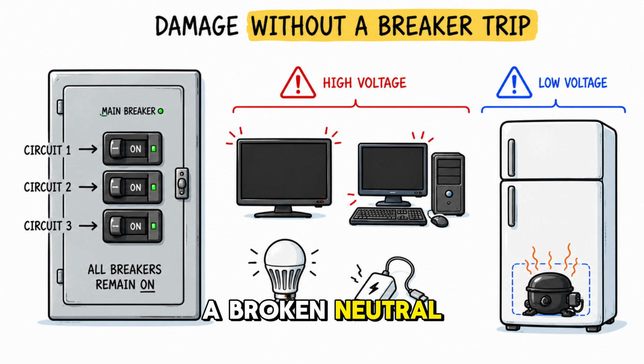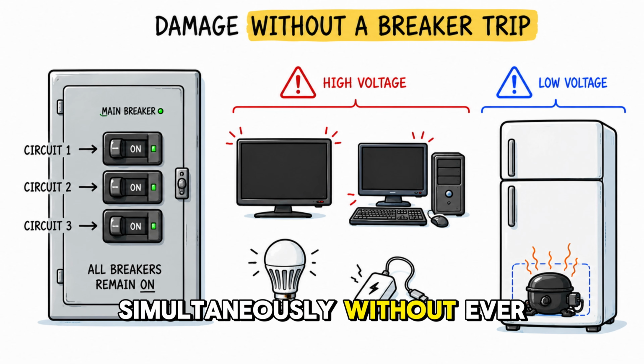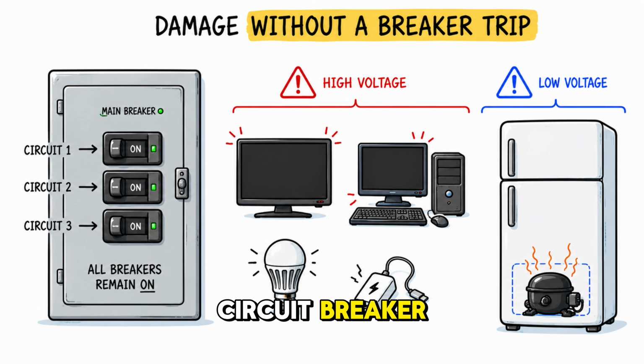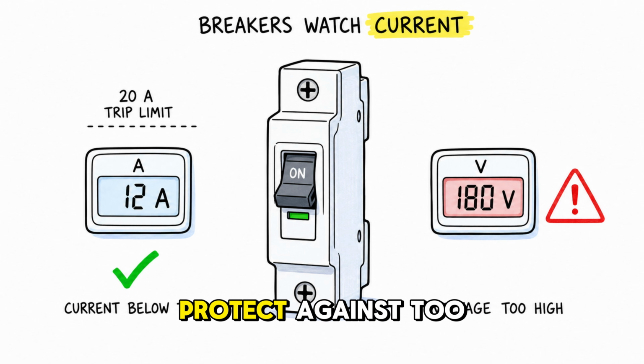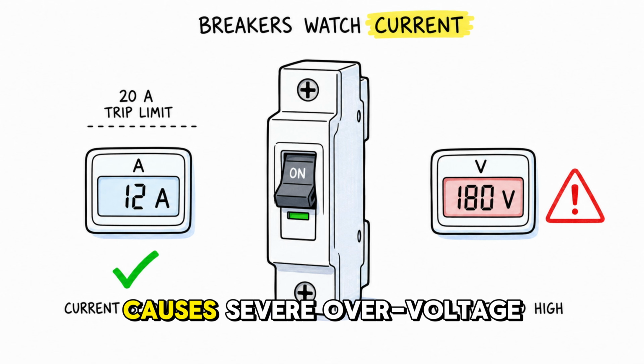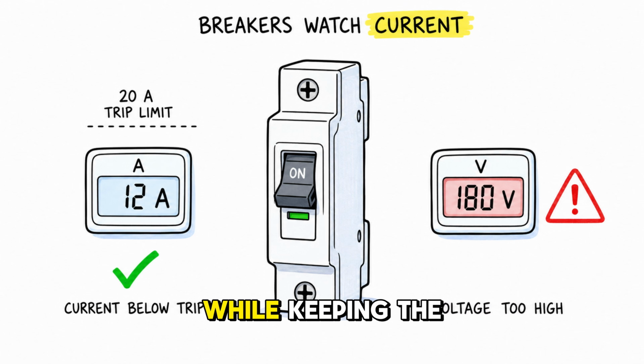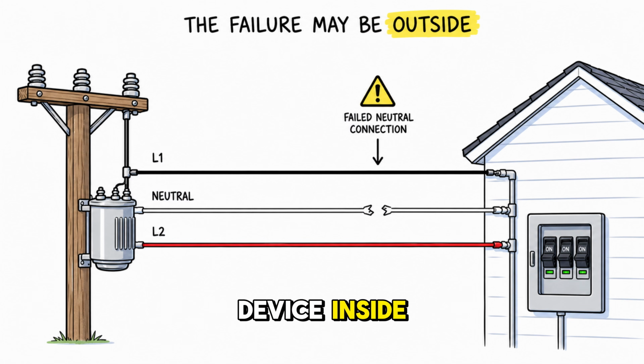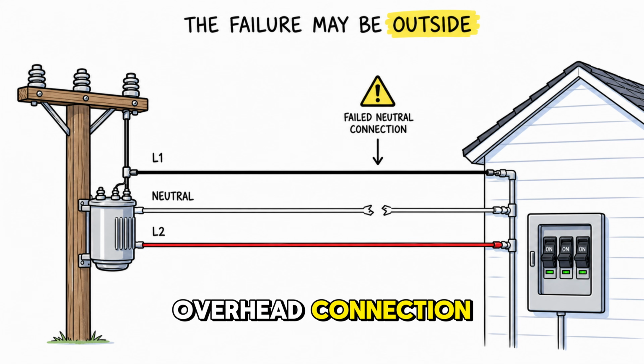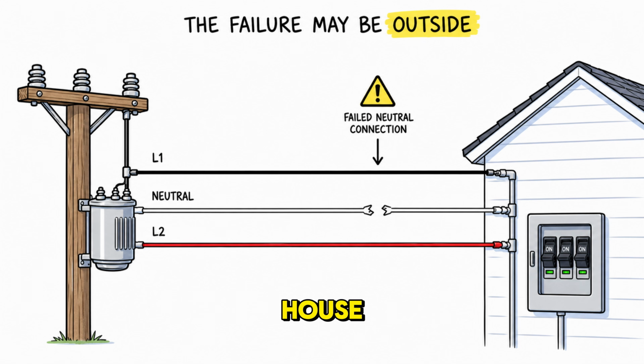This is why a broken neutral is one of the few electrical faults that can destroy almost every appliance in your home simultaneously without ever tripping a single circuit breaker. Standard circuit breakers only protect against too much current flowing at once. A broken neutral causes severe overvoltage while keeping the current levels completely normal. No standard protective device inside your panel will stop it, and it can happen at any moment at the overhead connection where the utility line attaches to your house.